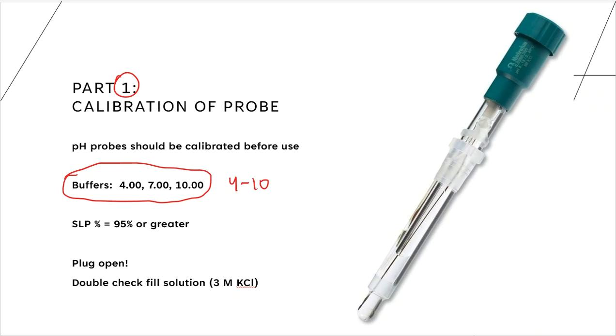All right. We never want a 1-point calibration, and that's because 1-point calibrations don't mean anything, right? We are pretending that that one solution is correct, and that one solution is exactly what that one solution needs to be. And if that one solution is off in any form or fashion, we have calibrated an entire probe based on that one thing and one thing alone. And it just doesn't quite make sense. Analytical wise, this is not what we're after.